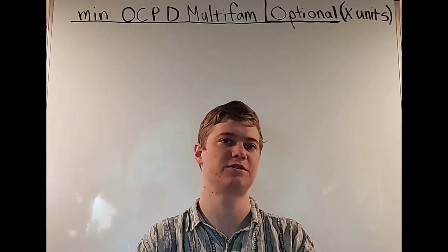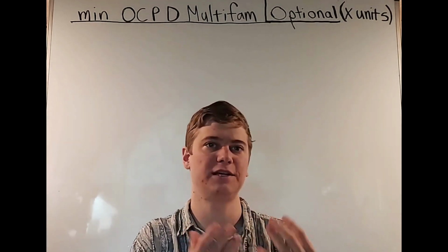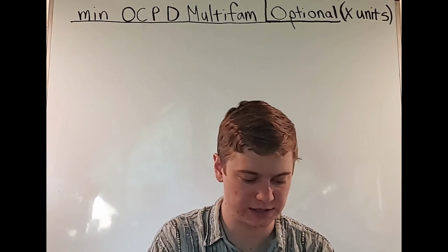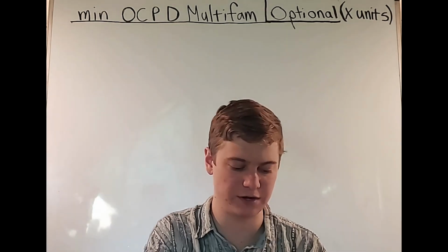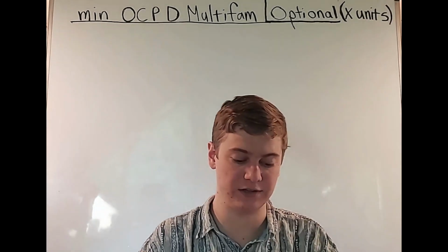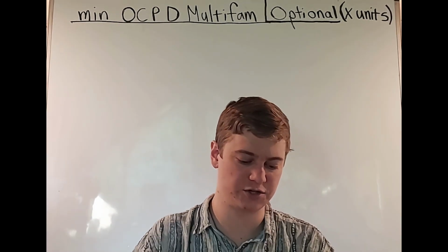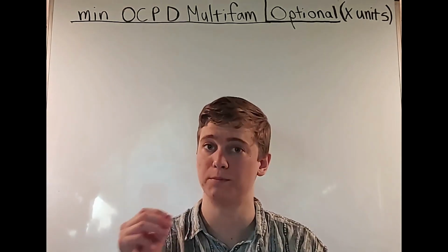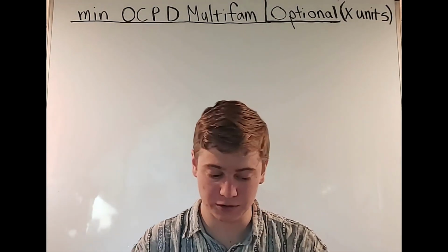Okay, a lot of times they're going to say we have dwelling units all supplied by one feeder. We have duplex units supplied by one feeder. So it's good if they tell you this, but a lot of times they're not going to tell you 2 or 3. And they're not going to directly tell you that. And then we see 2 and 3 are less common, but they're also good to know. So let's just look at them. Each of the dwelling units needs to have electric cooking equipment. In other words, what we call a range. And then we see number 3, that each dwelling has to have its own air conditioning or electric space heating or both.